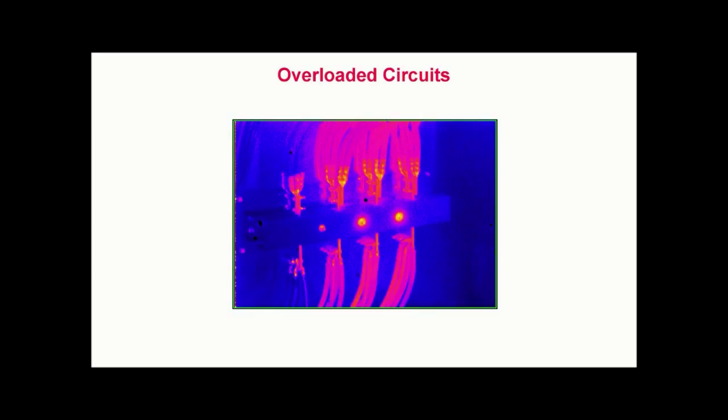Left undetected, overloading can cause premature failure of conductor insulation or lead to a fire. This image was captured during a quality assurance inspection of a new emergency generator system where the installed conductors were found to be undersized for the circuit load.